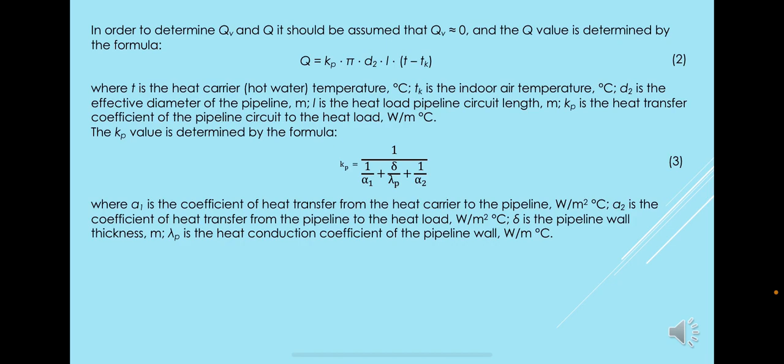D2 is the effective diameter of the pipeline, L is the heat loaded pipeline circuit length in meters, kp is the heat transfer coefficient of the pipeline circuit to the heat load. The kp value is determined by the formula here, where α1 is the coefficient of heat transfer from the heat carrier to the pipeline, α2 is the coefficient of heat transfer from the pipeline to the heat load, δ is the pipeline wall thickness in meters, and λp is the heat conduction coefficient of the pipeline wall in watts per meter degrees Celsius.